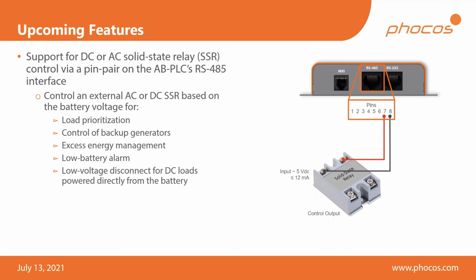Some common manufacturers are Crydom or Fotek, and there are many others. They all work roughly the same way. The major distinction, as I've said, is really to look out for whether you need an AC or a DC variant. You can't typically use the AC variants to switch DC loads and vice versa.